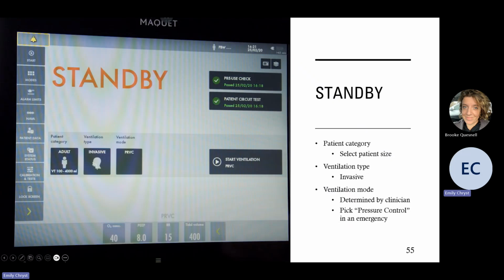So once you've done that and you've passed that, you're going to see the standby screen. And this is where you're going to select your patient type and all your ventilator types and settings. So you're going to select your patient size. For the most part, we're going to be venting in pediatric or adult, not often neonate. You can see the tidal volume here. So these ventilators aren't going to tell you by weight. They're going to tell you by tidal volume. 100 correlates with maybe a 20 kg patient max at lower tidal volumes. So most of your patients are going to be adult or peds.